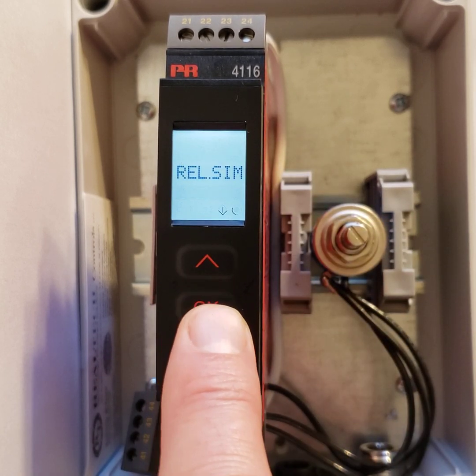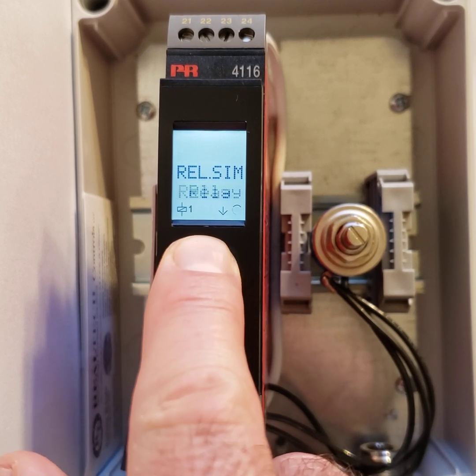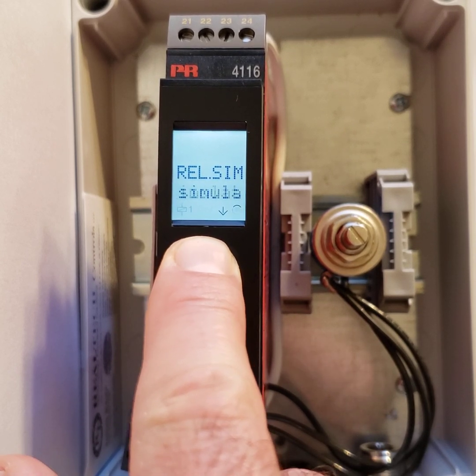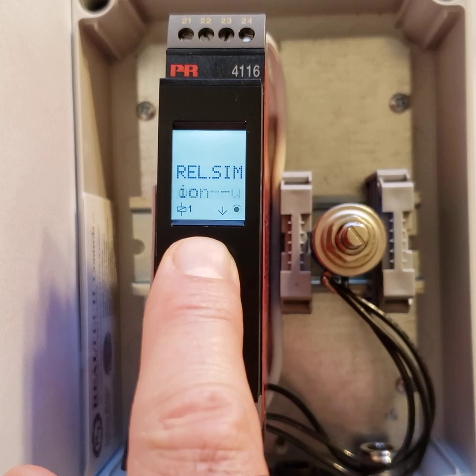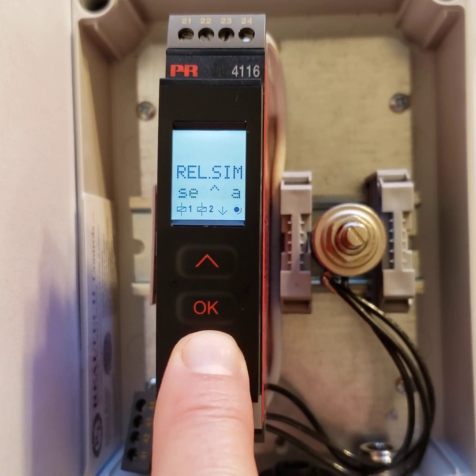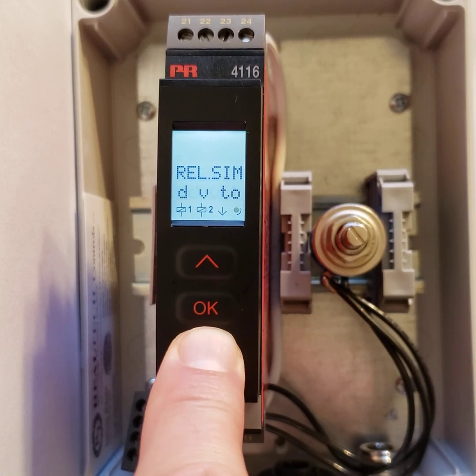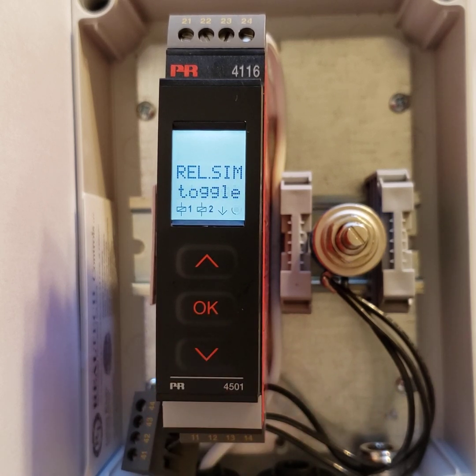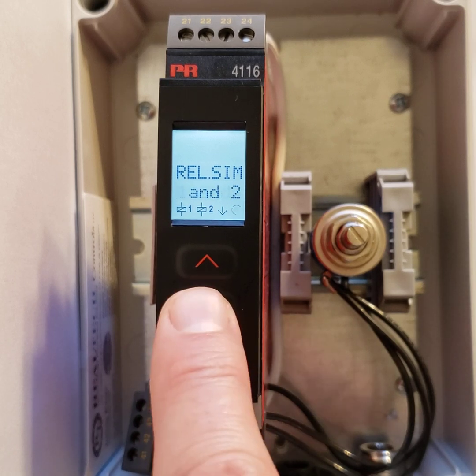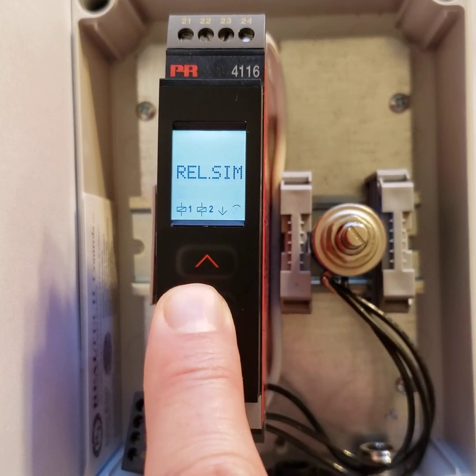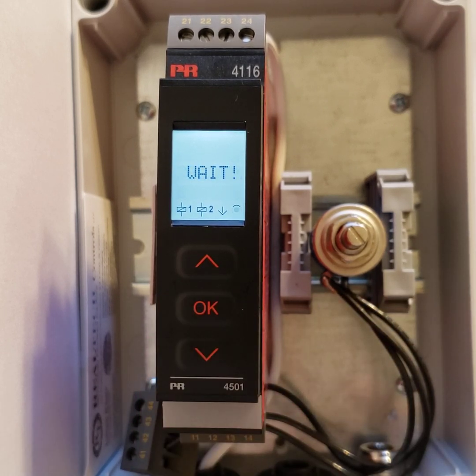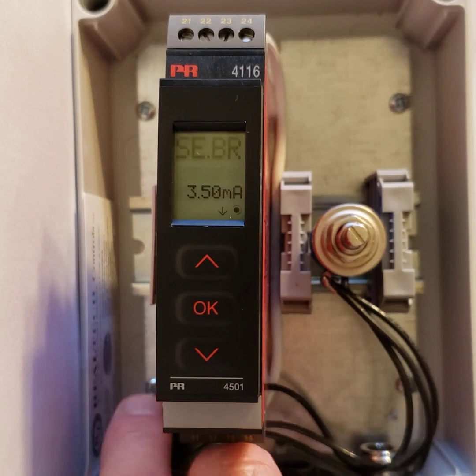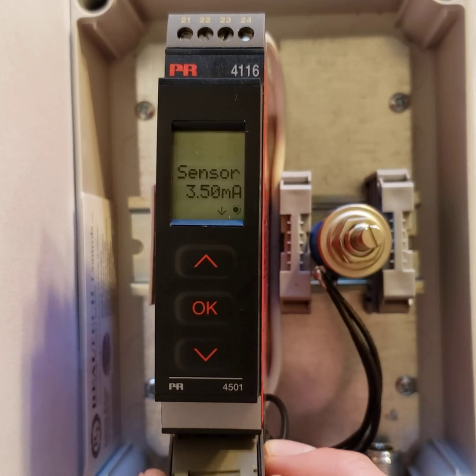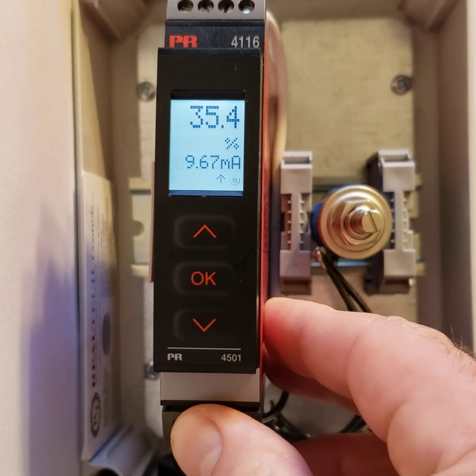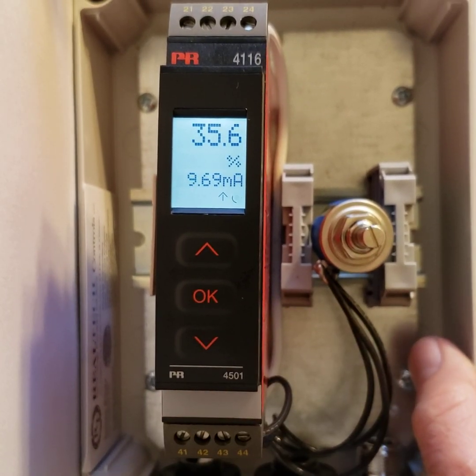If I just want to simulate my relays, you push it again. And you can see relay one changes when you push the up arrow, and relay two alternates when you push the bottom arrow. So this is for complete simulation of your milliamp outputs and your relays without anything being connected. Push OK and it goes back to the normal reading mode. And if I connect my potentiometer once more, there we go, it comes back to normal.